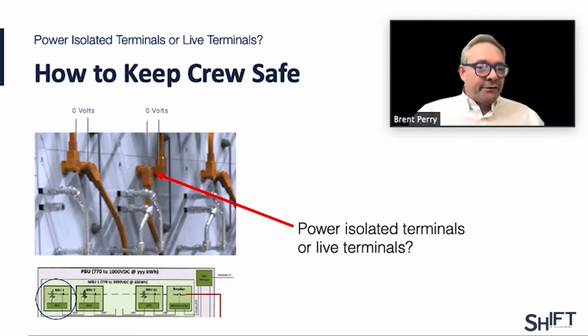We believe strongly this is going to become the ultimate standard to make sure that you both limit the voltage risk that you manage to whatever a single module voltage is, in our case 100 volts DC, and systems that are quite often up to 1500 volts DC. That's a very important feature. And also that when someone does make a disconnection, that's going to cause the whole system to shut off so that there is no voltage at the terminals. This is also good for transit, so there is no voltage on these terminals when you're transporting, installing, or hooking up. It's only when everything is completely closed system that the batteries can actually deliver energy and power to the grid.